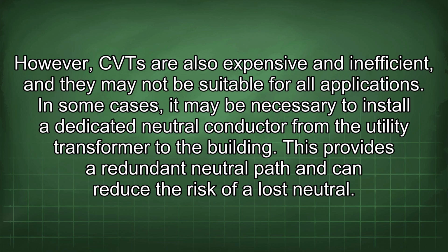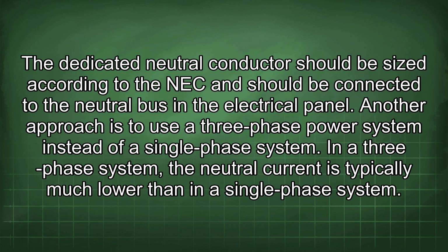CVT can provide a high degree of voltage regulation and can protect equipment from voltage surges and sags. In the event of a lost neutral, a CVT can help to maintain a stable voltage on the load side, preventing damage to equipment. However, CVTs are also expensive and inefficient, and they may not be suitable for all applications.